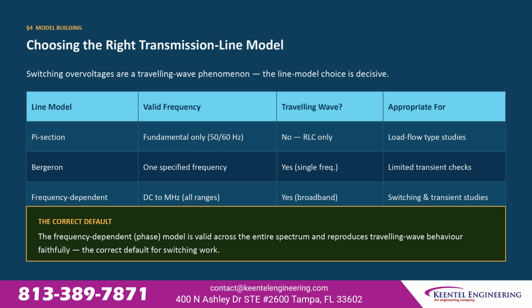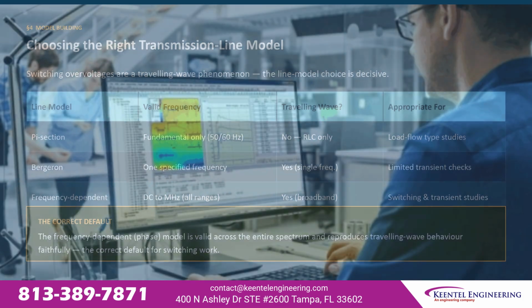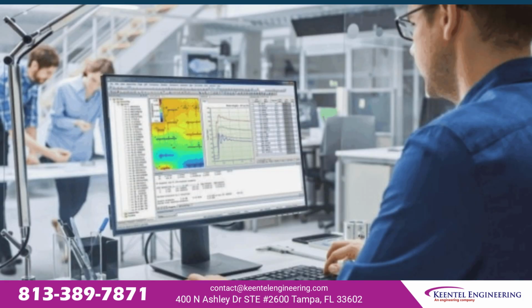3 line models exist in PSCAD/EMTDC. Only one is appropriate for switching work. The PI section model is a lumped RLC circuit, valid only at fundamental frequency. It cannot reproduce traveling waves and is not suitable for transient studies. The Bergeron model supports traveling wave propagation, but only at a single specified frequency, suitable for limited checks, not a full statistical sweep. The frequency-dependent model is valid from DC to the megahertz range. It reproduces traveling wave behavior faithfully across the entire spectrum, and is the correct default for switching overvoltage work. Using anything else introduces errors that cannot be corrected in post-processing.